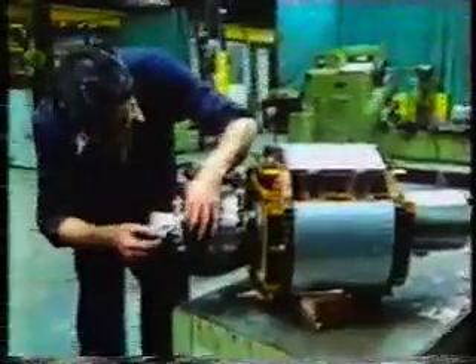The exciter rotor is built individually before being fitted to the main rotor shaft. The face of the rotor is turned to the diameter that will give the required finished air gap between rotor and stator. Another sub-assembly fitted to the main rotor is the rotating rectifier, constructed from aluminium heat sinks. It carries 6 high-quality diodes and is fitted with a field suppression device. Inspection is carried out at every stage of manufacture.